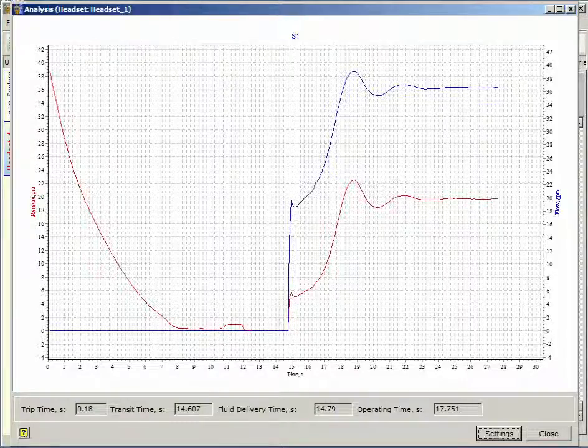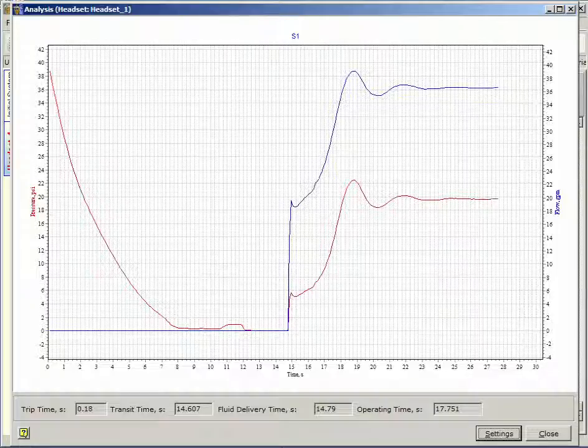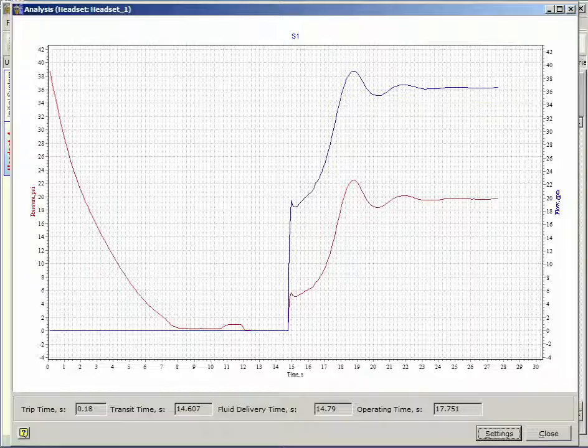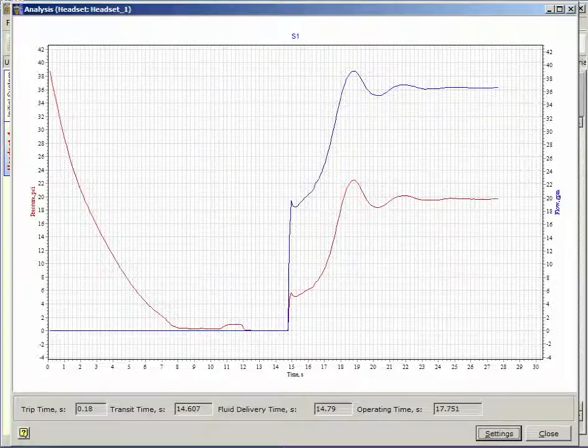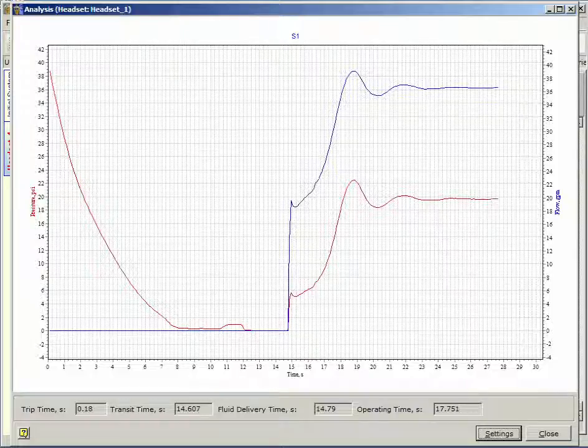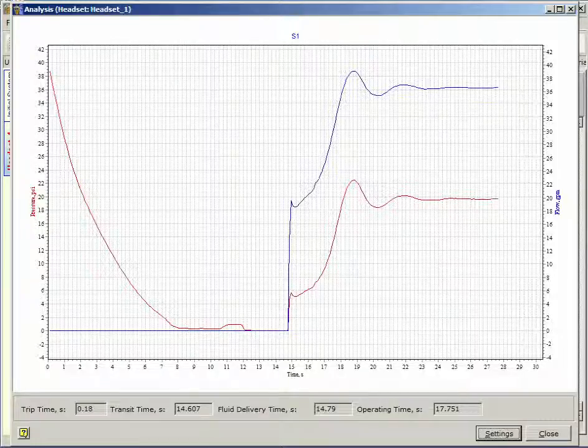The pressure oscillates as the water flow increases. The water pressure stabilizes above the specified minimum and the calculation continues for the period of the monitoring time, which in this case was set to 10 seconds. The trip, transit, fluid delivery and operating times are displayed at the bottom of the screen.